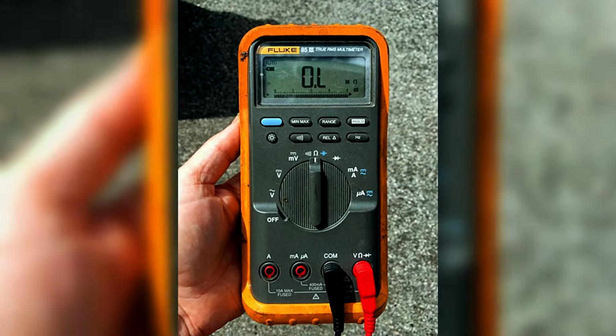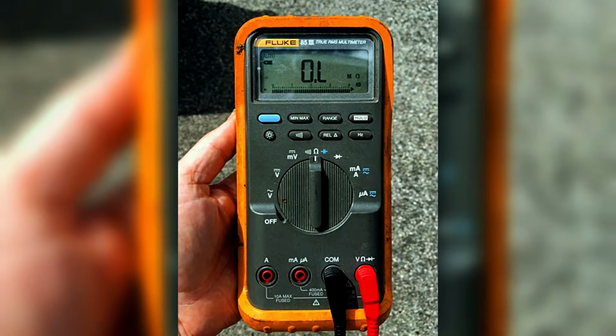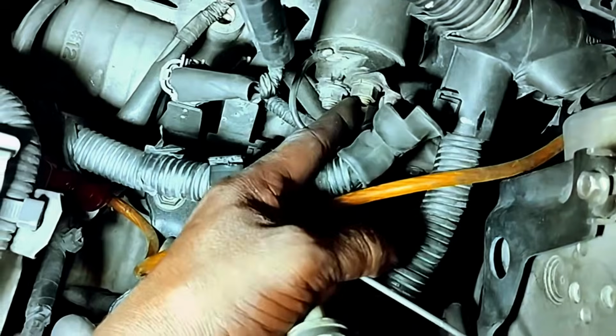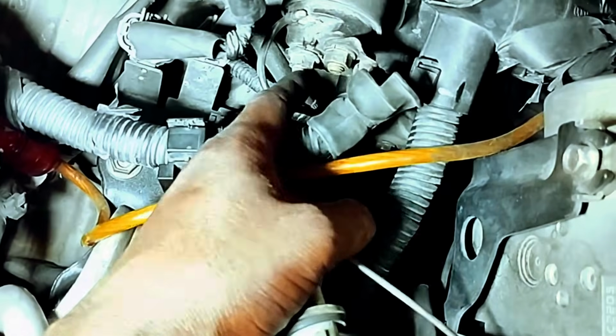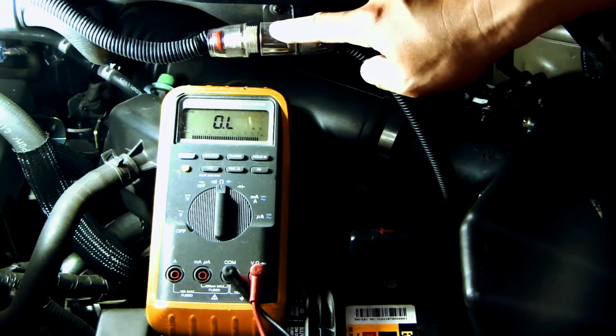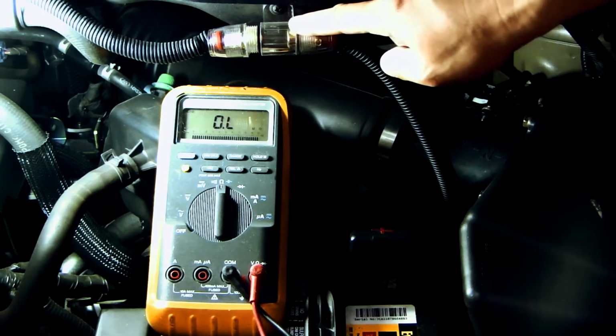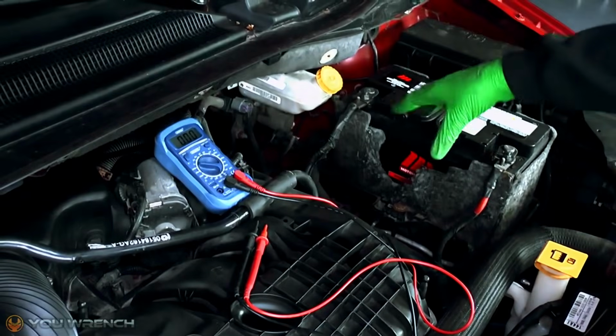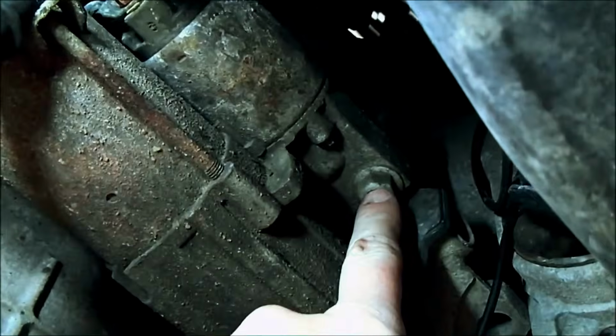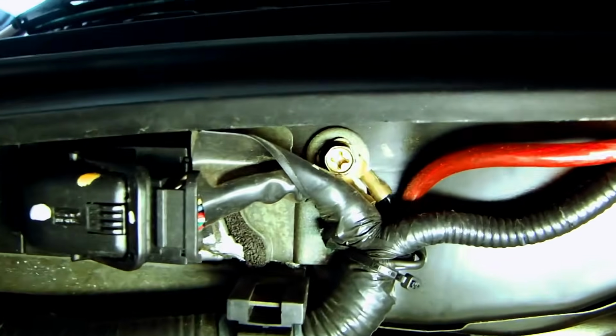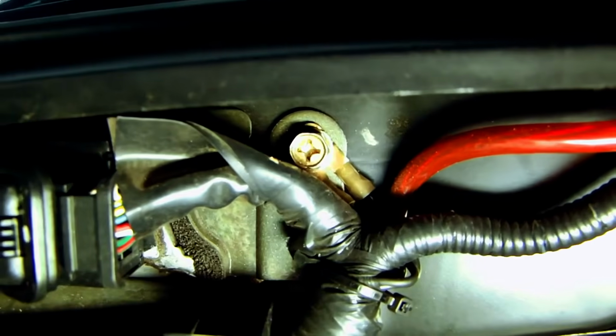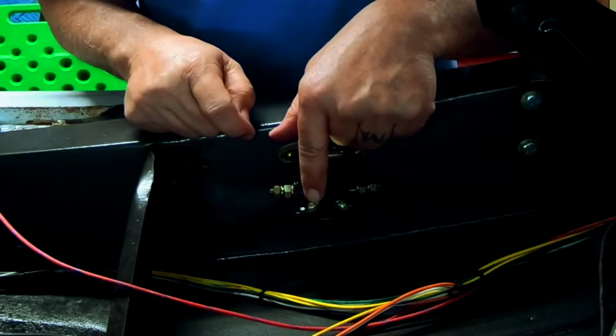Set the multimeter to resistance, ohms, or continuity mode. Place one probe on the starter motor housing and the other on the engine block or the battery's negative terminal. The reading should show very low resistance, ideally close to 0 ohms, or a clear continuity signal. High resistance or no continuity indicates a poor ground path. This can be caused by corrosion, loose mounting bolts, damaged ground straps, or paint and rust between the starter and engine block. Correct any ground issues before condemning the starter motor itself.